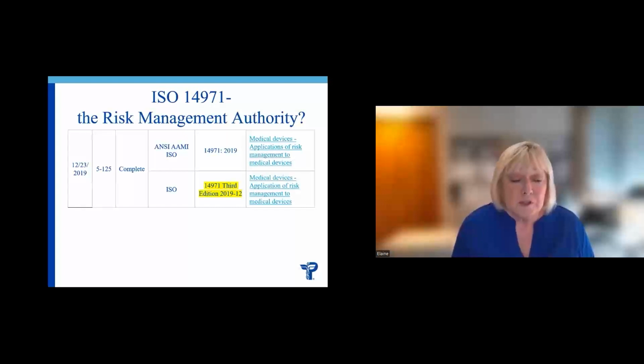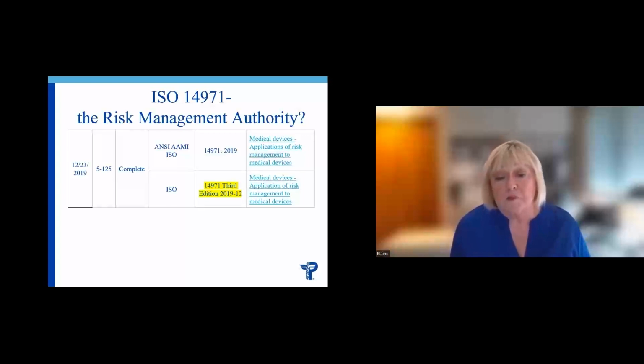Now, this is a snapshot off of the FDA website, and I typed in the word risk, and this is the row that came up that says FDA recognizes these two standards and gives you a risk recognition number, 5125. And so when you're making your application, you want to be able to say to FDA, I did my risk management according to these standards. And you keep an eye on the idea of whether or not that standard has been reissued or not.